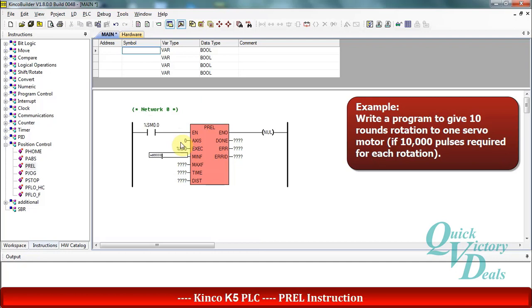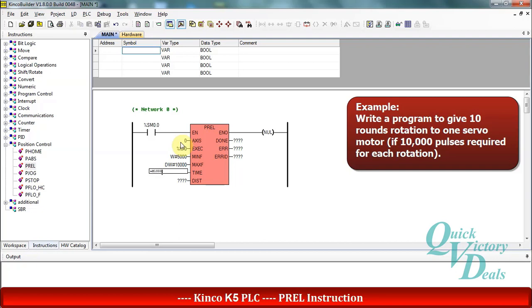I will set minimum frequency to 5 kilohertz and maximum frequency to 10 kilohertz, and also the acceleration time one second. And in the distance operand I will enter 10 multiply 10,000.